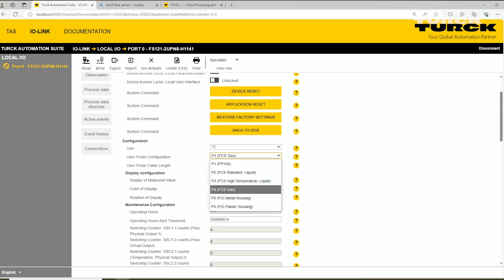P4 is for gas, and we also have some inline FCI models — one with metal and one with plastic available. It may also be possible that in future we will add more groups if the requirement increases. Here you can also give the cable length and change it as per your requirement — it can be done up to 30 meters between the FS1-2-1 and the mounting position of the flow probe.